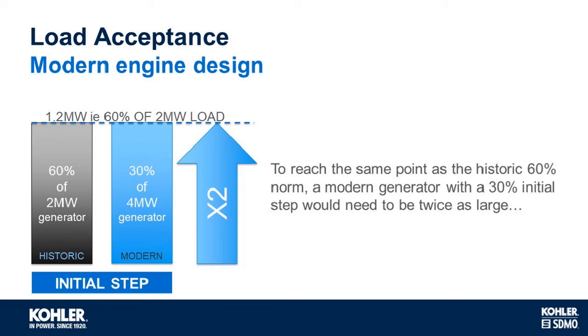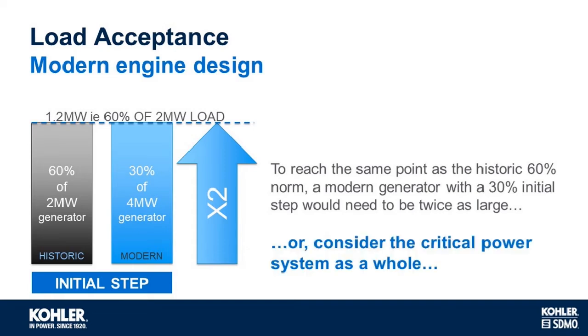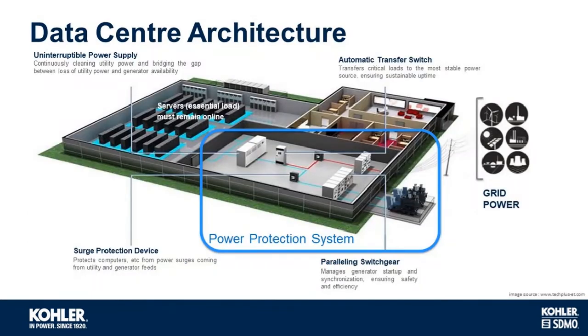So to reach the same point as the 60% historic norm, a modern generator with a 30% initial load step could be significantly oversized. In fact, it could be twice as large in the worst case scenario when taking into account all the application and site requirements. Or we consider the critical power system as a whole.